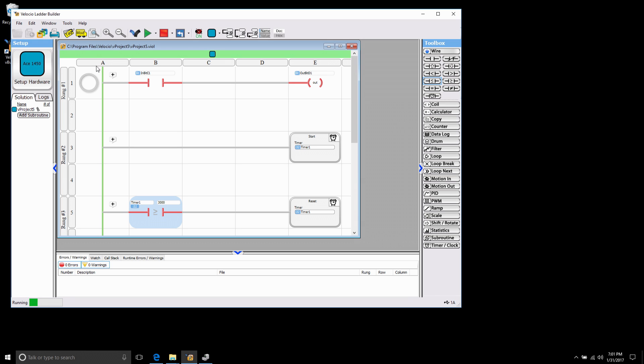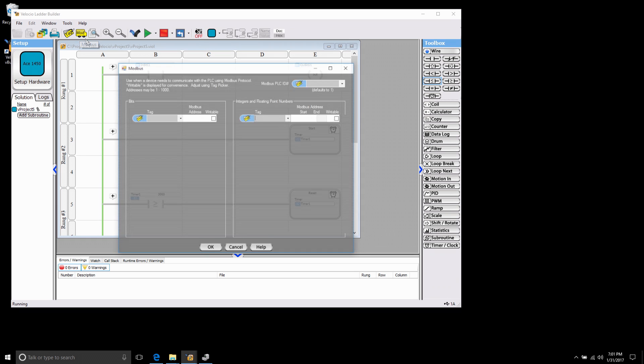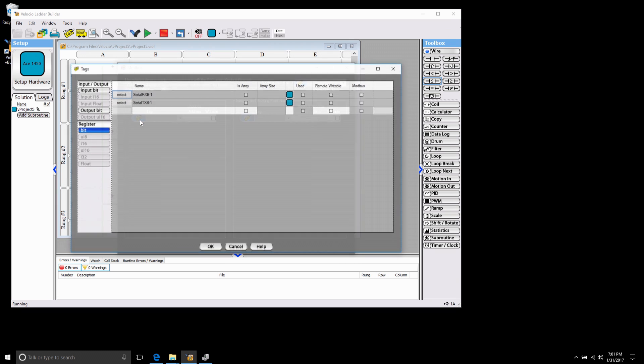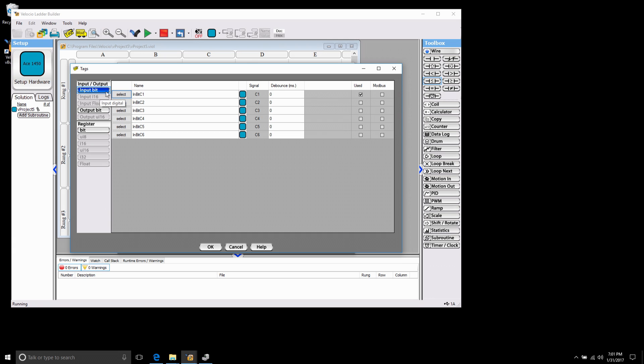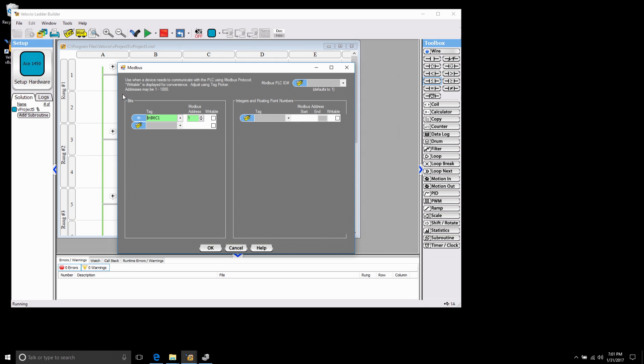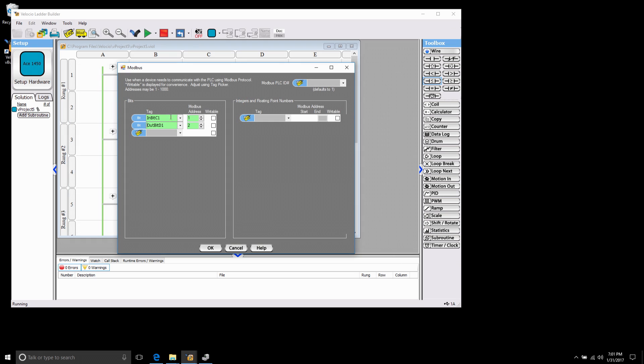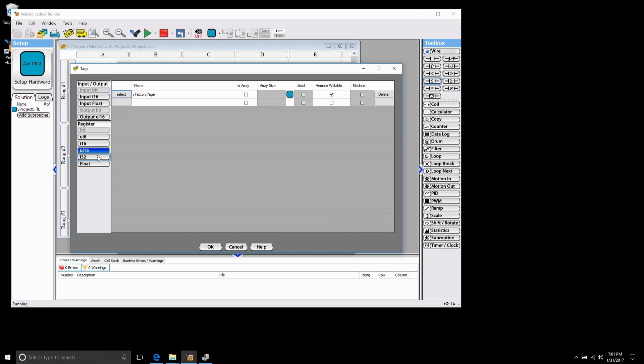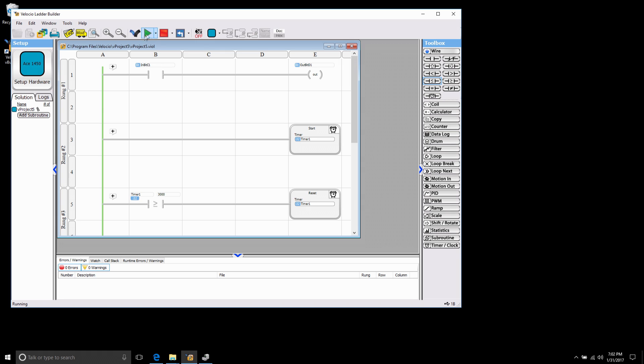So now what I want to do is map my Modbus registers. First thing I'm going to do is turn off debug mode. Come back to Modbus and I'm going to map some of my tags to Modbus registers so that Advanced HMI can access them through the Modbus driver. The first thing I'm going to select is my input bit and then output bits and you see right here it's address one and two for the input and output. Now for the timer I'm going to come over here to integers and floating point. Select my timer and that gives me Modbus start address one and end address two because it is a 32-bit. Modbus registers only 16-bit, it needs these two registers.